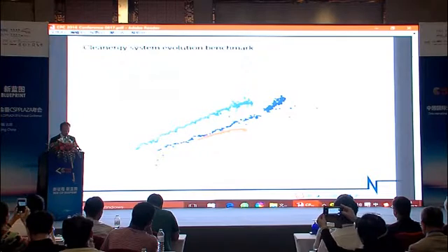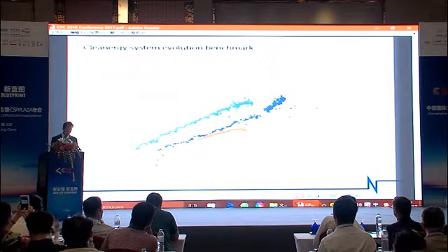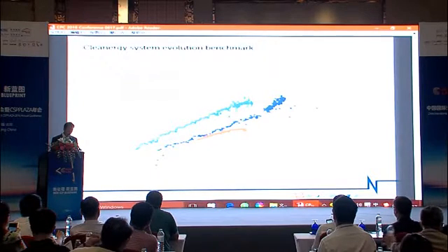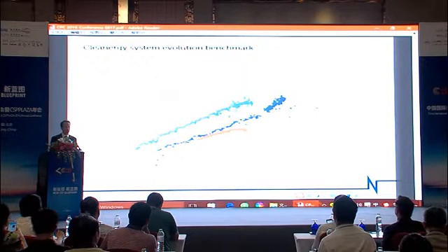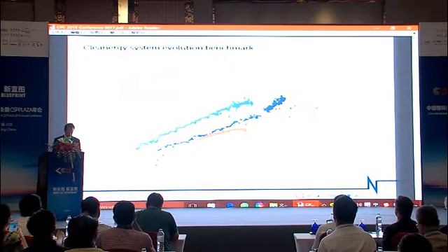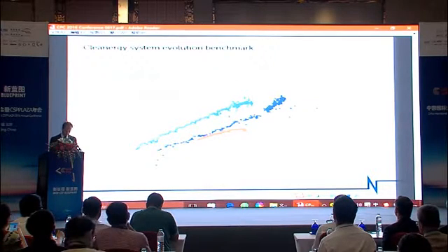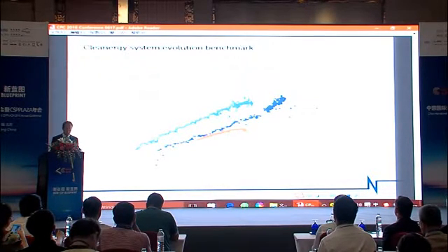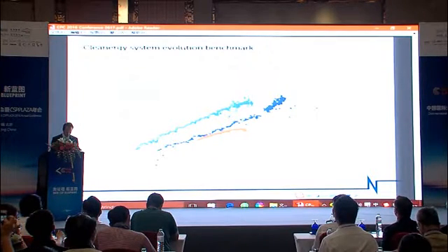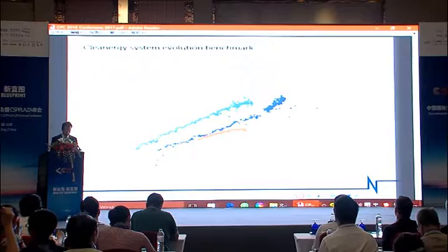I would like to direct your attention to the top curve, the lighter blue dots. 最上面的这条线呢，是我们最新的斯特林发动机的输出波形。You'll see that it starts its operations at around 150 DNI. 那么这个新的斯特林发动机大概在 DNI 150的情况下就可以自动运行。Reaches about 9.5 kilowatts at below 600 DNI.